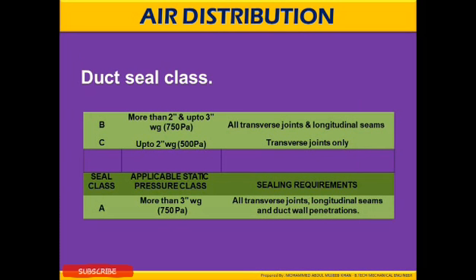Duct seal classes. More than 2 inch up to 3 inch of water gauge, which is 750 Pascal: all transverse joints and longitudinal joint seams. The class C, up to 2 inch of water gauge, which is 500 Pascal, is transverse joints only. Seal class A, application static pressure class more than 3 inch, which is 750 Pascal: all transverse joints, longitudinal seams and duct wall penetrations.